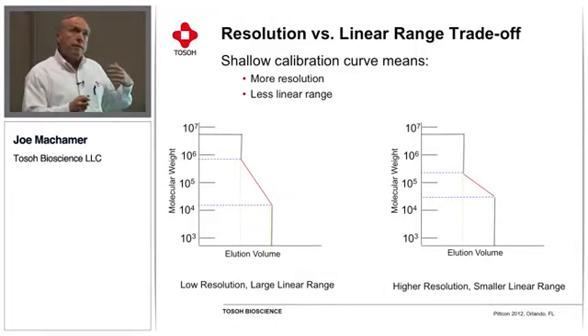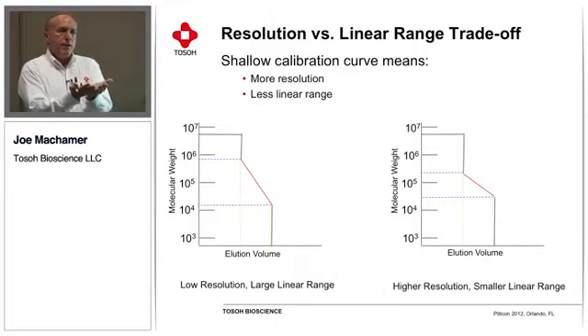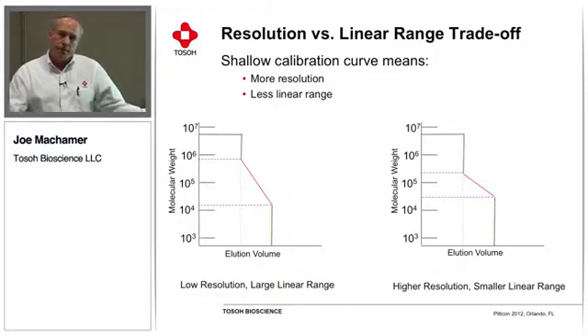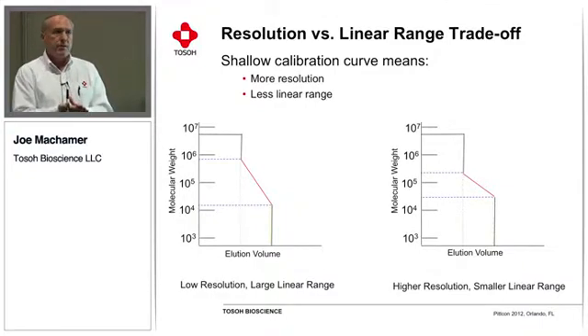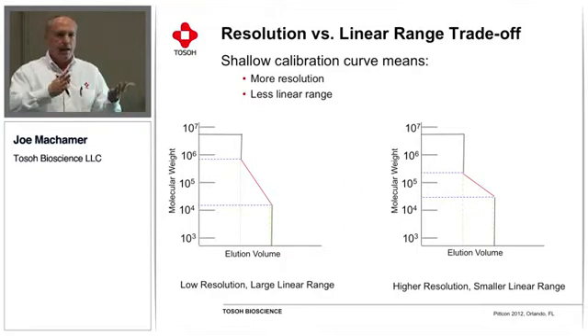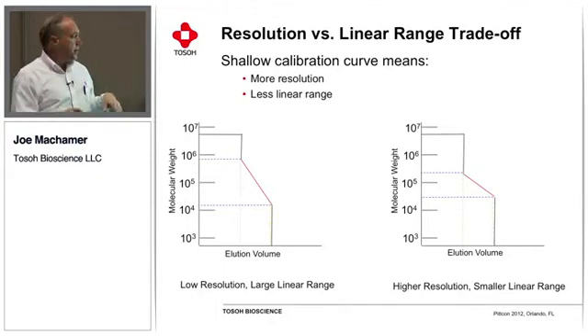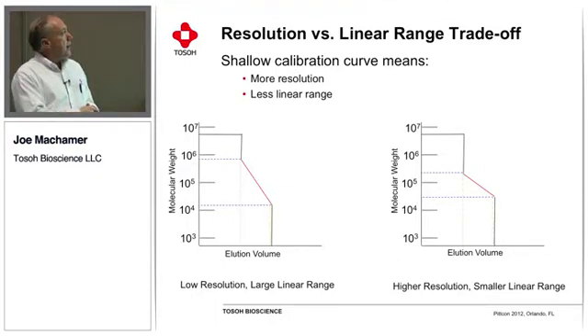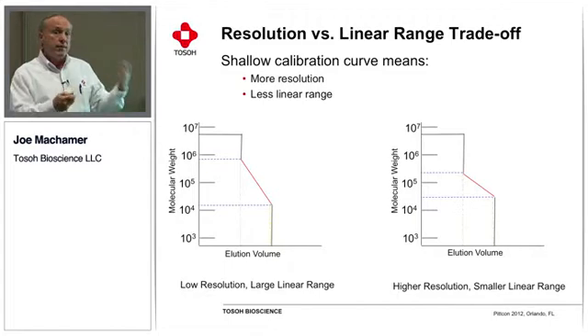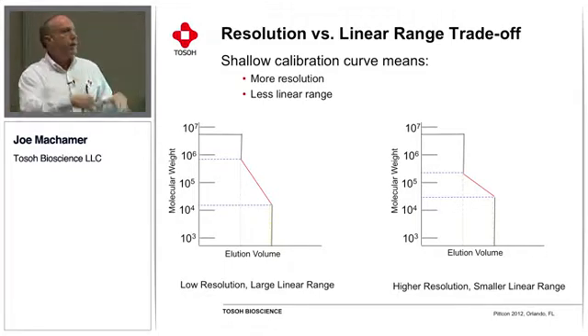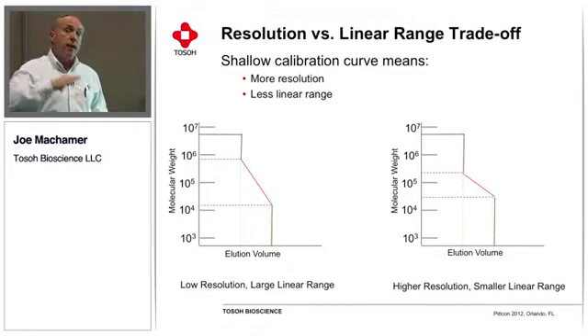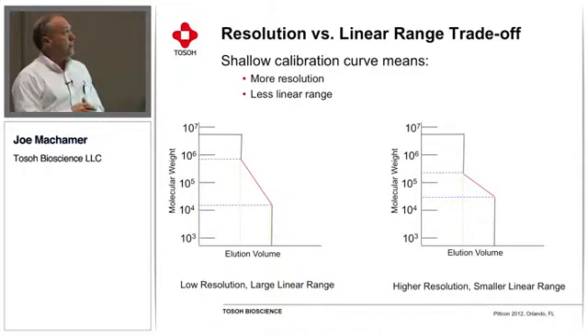And if you look at calibration curves in catalogs from Tosoh or any other company that makes GPC columns, typically they'll have 8 or 10 or 12 different types of columns and their calibration curves laid on top of each other. And a pattern that you can see when you look at that is there tends to be a trade-off between the resolution that a particular column can provide and the linear range across which that resolution can be used. And so that's what I'm trying to show here with these couple of curves.